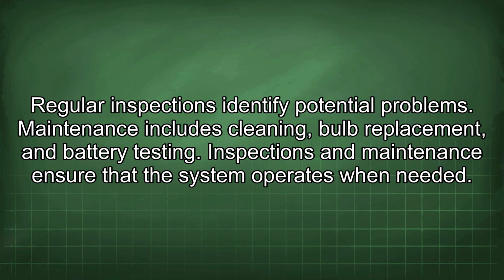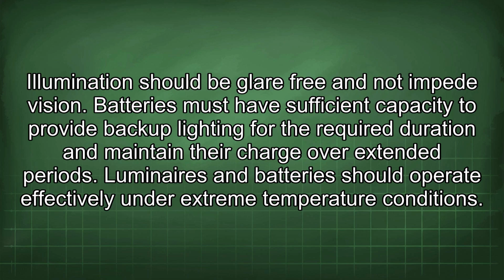Maintenance includes cleaning, bulb replacement, and battery testing. Inspections and maintenance ensure that the system operates when needed. Illumination should be glare-free and not impede vision. Batteries must have sufficient capacity to provide backup lighting for the required duration and maintain their charge over extended periods. Luminaires and batteries should operate effectively under extreme temperature conditions.